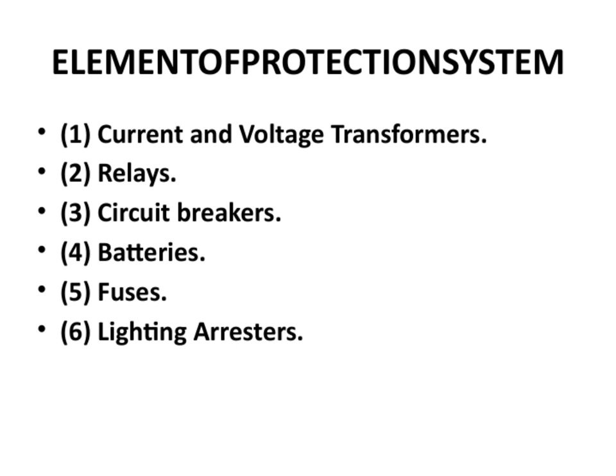Let's talk about current transformers. They typically consist of at least 2 secondary windings. The first winding is generally designed for measurement purposes, allowing us to accurately read current levels. The second winding, on the other hand, is used for protection, helping safeguard the system by providing reliable signals for protective devices.